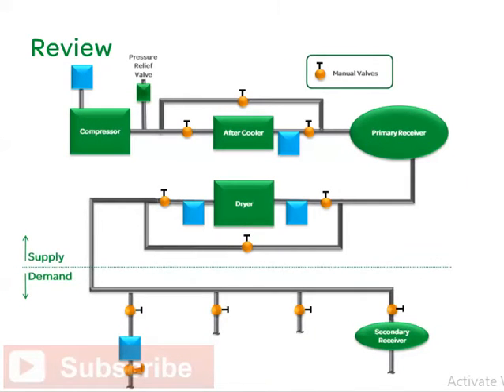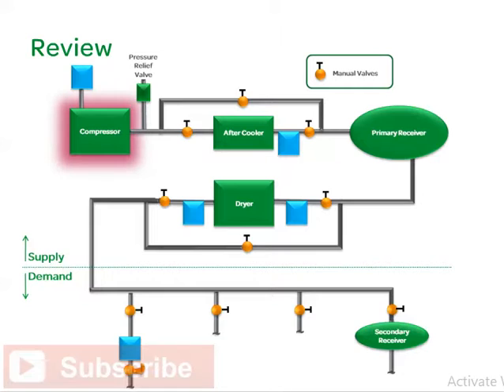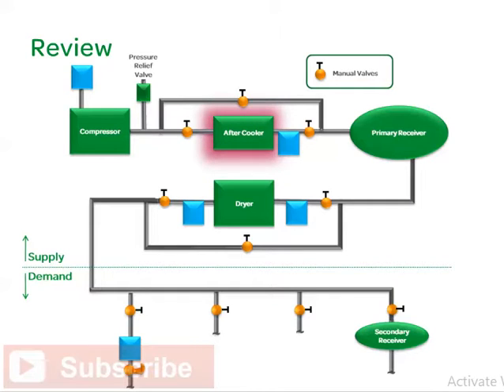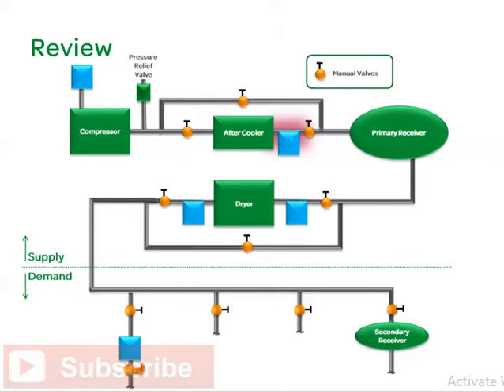The following components may be found as part of the supply side of a compressed air system. Air inlet filter, which filters particulate and water of incoming ambient air. The compressor, discussed in Compressed Air Systems 2, Compressor Types and Selection, compresses atmospheric air into a useful and versatile utility. During the process, lubricants could be present. After cooler cools compressor discharge air and condenses up to 70% of the moisture drawn into the compressor. Separator separates condensed liquids leaving the after cooler. Automatic drain automatically drains condensate out of the separator and other conditioning devices. Primary receiver provides storage for compressed air supply in case a compressor fails. This can give time for an additional compressor to start up with little pressure loss and no interruption in production.